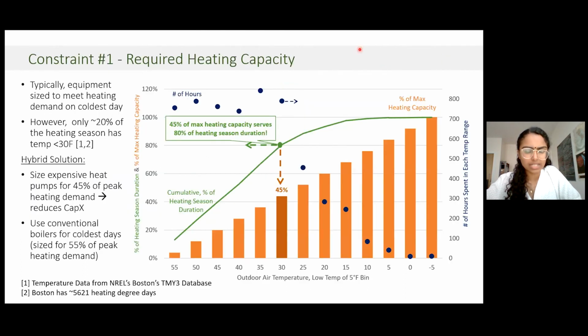What we'll be talking about first is the first constraint, so the required heating capacity. As we've mentioned earlier, as temperatures decrease, we need more heating capacity. However, the number of hours that we actually spend in each of these temperature bins doesn't vary in the same way. What we've noticed is that for temperatures that are greater than 30 degrees Fahrenheit, we spend roughly 700 to 800 hours in each of these 5-degree temperature bins. However, there's a sharp drop-off for temperatures colder than 30 degrees Fahrenheit, to the point where you can spend between 10 and 15 hours in an average year at these coldest temperatures.